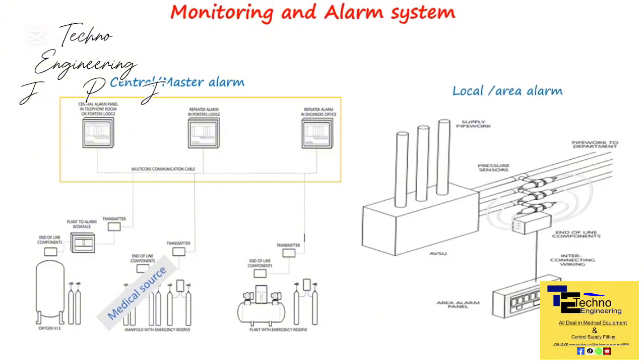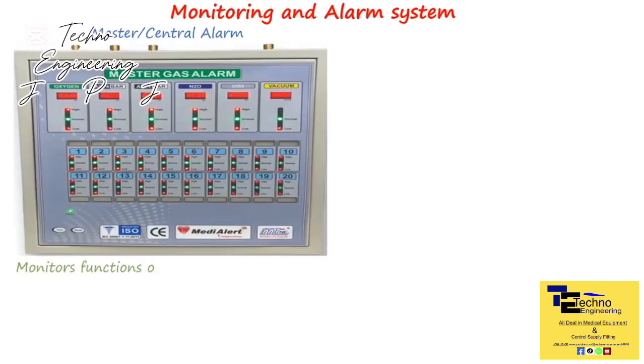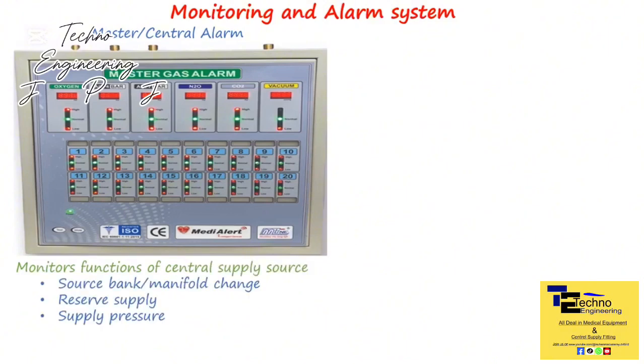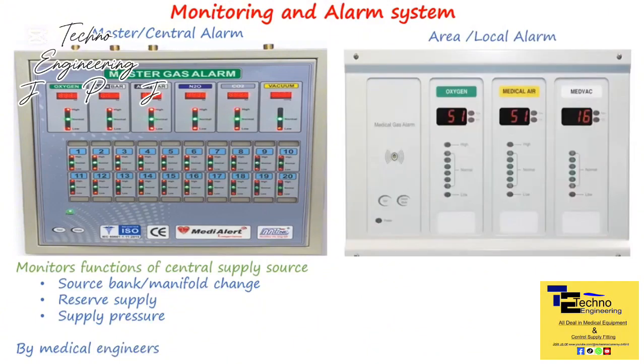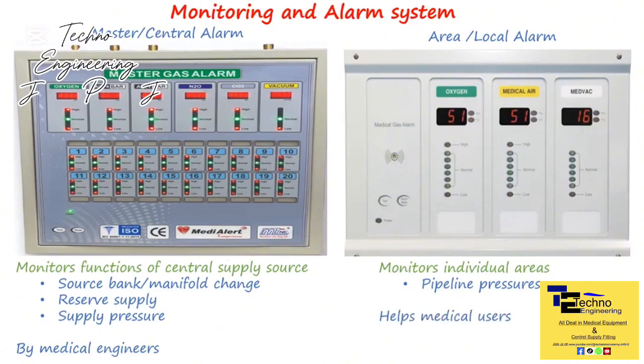Area or local alarms, as the name implies, are located peripherally in wards, operation theaters, and ICUs. Central alarms monitor supply source functions like cylinder replacement, main supply levels, reserve supply activation, and mainline pressure deviations on alarm panels or a computerized system. Medical gas engineers keep a close eye on these alarms. Area alarms monitor pressure in the pipeline, indicated on a locally mounted indicator panel. These alarms notify end users of any pressure change in their workplace.